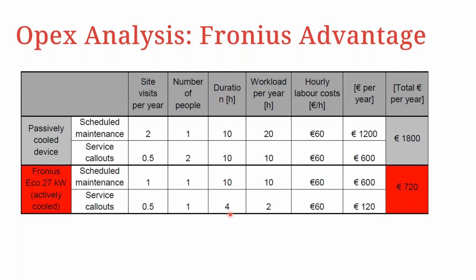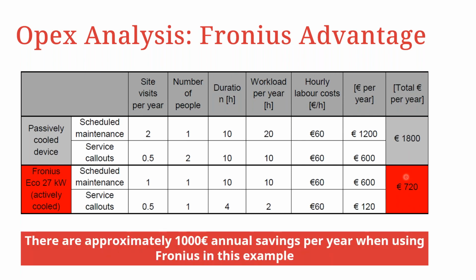As you can see, that of service callouts is quite less. In fact, less than half of that of the passively cooled device. So at the end of the day, once all the costs are accumulated, we have an accumulated cost of 1,800 euros for the passively cooled device, while I have an accumulated cost of 720 euros for the actively cooled Fronius Eco device, thereby having a slightly above 1,000 euro annual savings per year when making use of Fronius Eco 27 in this example.